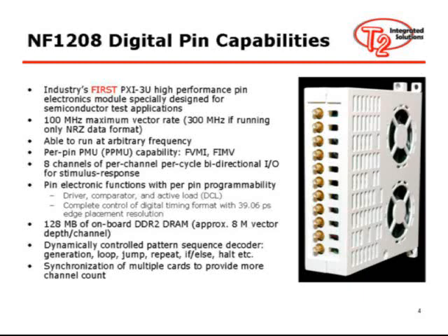We are able to do time set change on the fly for this module. Besides, this module is able to do real-time onboard hardware comparison for DUT data that is being captured. It has advanced trigger and pattern sequencing capability, and if you need more channels, it supports multiple module synchronization.